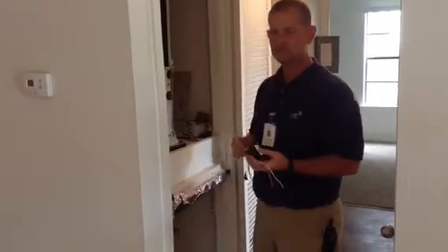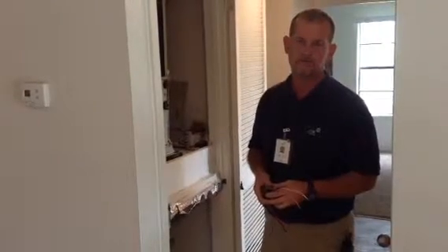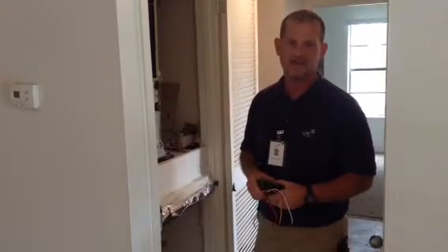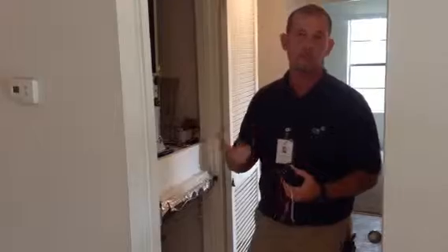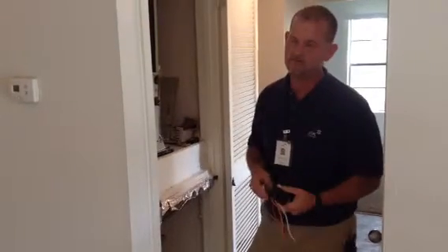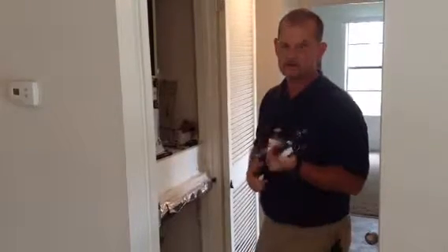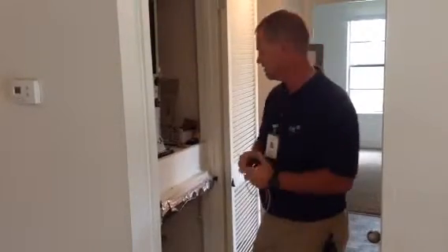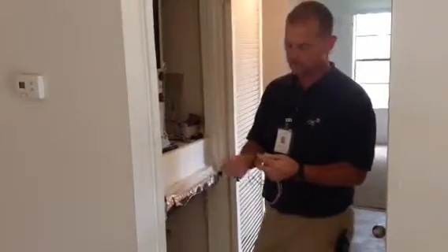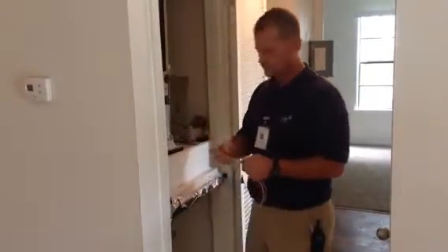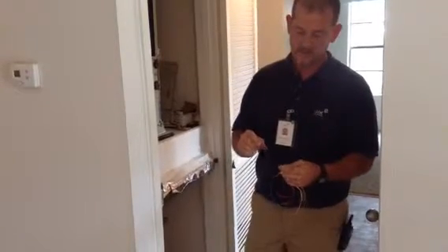One thing you always want to do in these older systems is put in an inline fuse. The newer systems have boards, and the boards have a little 3 amp fuse in there, so it blows before it blows the transformer. Older systems don't have the fuse, so one of the best practices is, if you're in there, put in an inline fuse. It's real easy. Basically, cut one of your 24 volt wires off. You're going to get 2 female connectors.